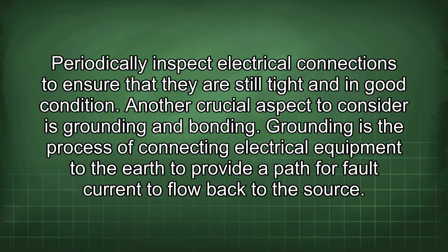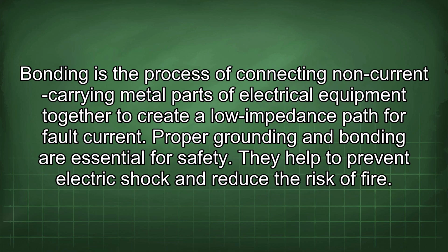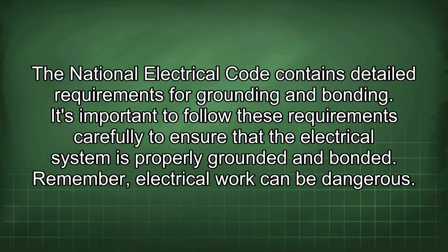Another crucial aspect to consider is grounding and bonding. Grounding is the process of connecting electrical equipment to the earth to provide a path for fault current to flow back to the source. Bonding is the process of connecting non-current carrying metal parts of electrical equipment together to create a low impedance path for fault current. Proper grounding and bonding are essential for safety. They help to prevent electric shock and reduce the risk of fire. The National Electrical Code contains detailed requirements for grounding and bonding. It's important to follow these requirements carefully to ensure that the electrical system is properly grounded and bonded.